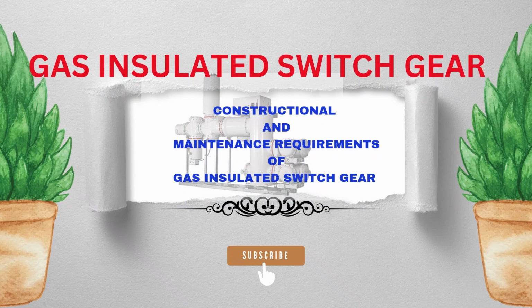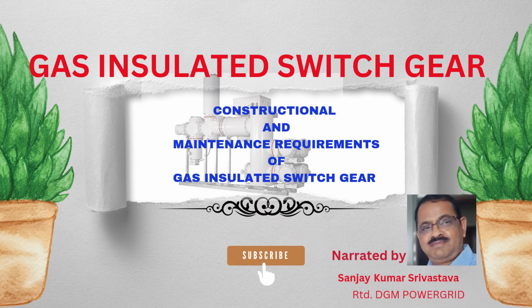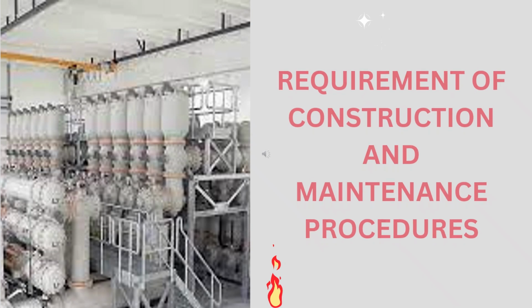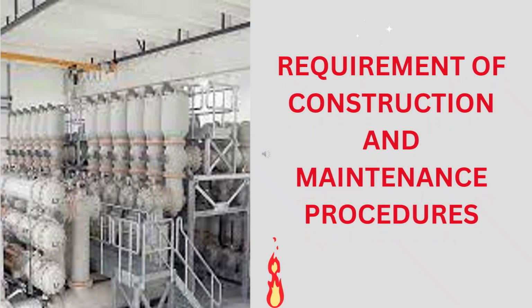Constructional and maintenance requirements of gas-insulated switchgear. Construction and maintenance procedures due to its enclosed design and use of SF6 gas. Construction involves modular, hermetically sealed compartments for different components, minimizing the risk of gas leaks and internal arcs. Maintenance focuses on regular inspections, electrical testing, SF6 gas analysis, and cleaning with specialized procedures for gas handling and leak detection.